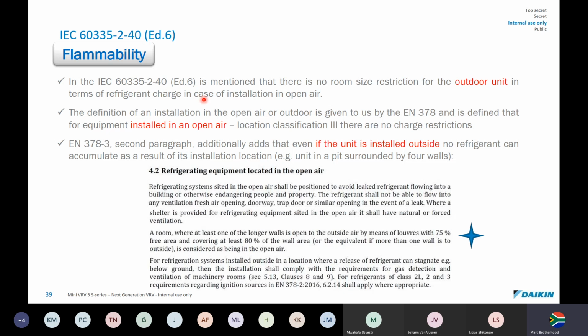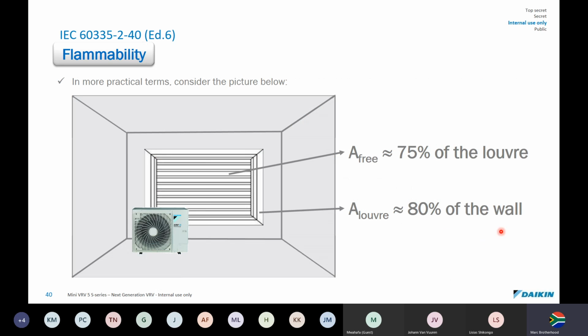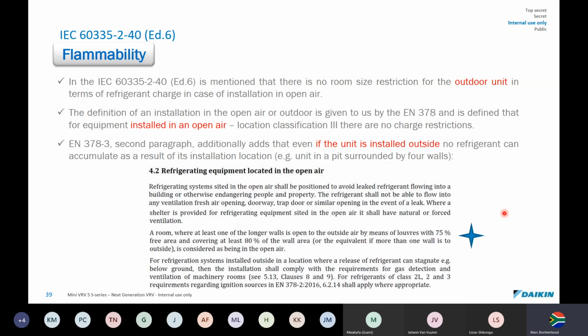I'm not going to go through this whole standard, but they do give definitions of a room here. That's why I've put this little star. But what am I getting at here? I'm getting at this. If you don't put your condensing unit outdoors and you put it inside, say on a parapet in a block of flats where it doesn't want to be seen, this is the minimum dimensions you can use. Or else if this leaks, it's not free to atmosphere. So you have to use a ratio. 75% of the louver must be free and the louver must be 80% of the wall. But I'll share this presentation with you guys and you can go through and read up on these standards.